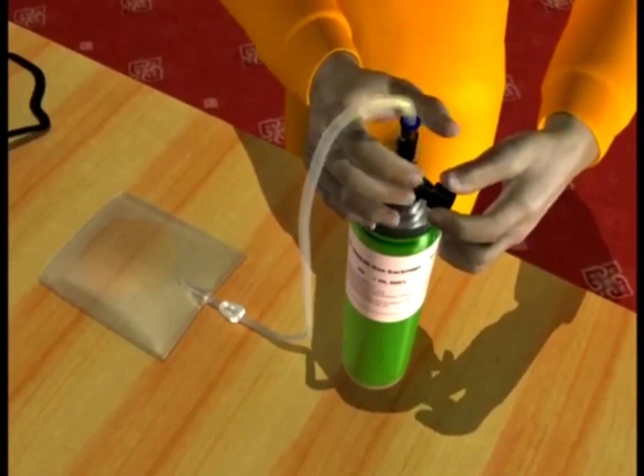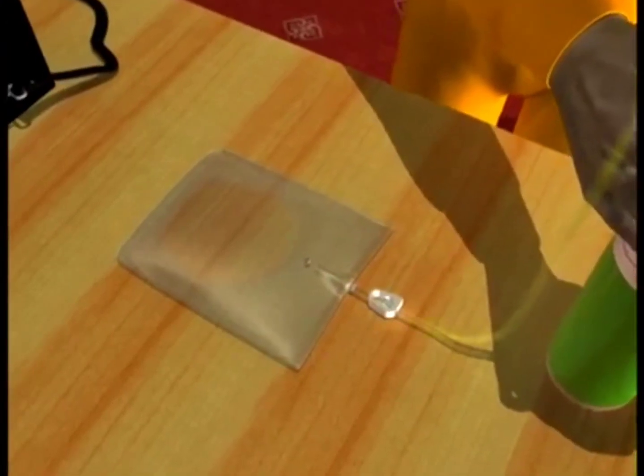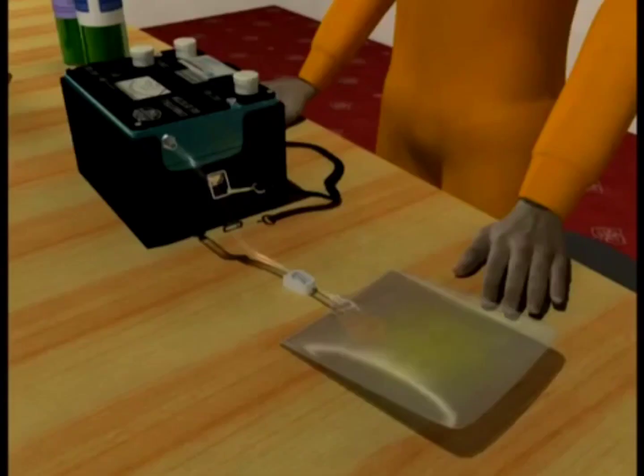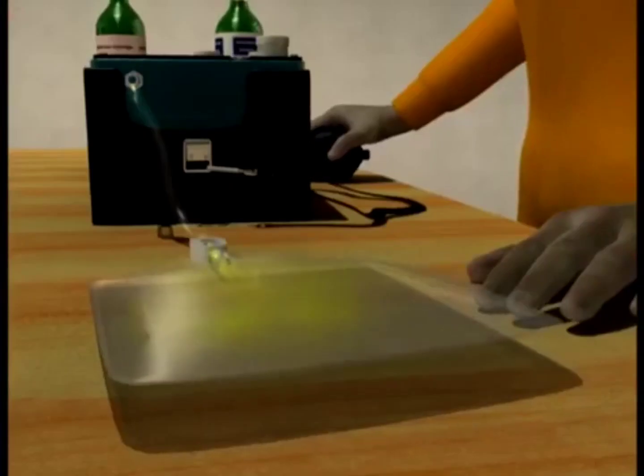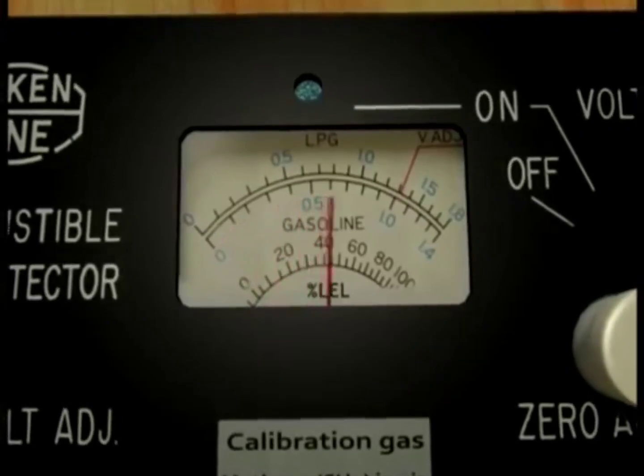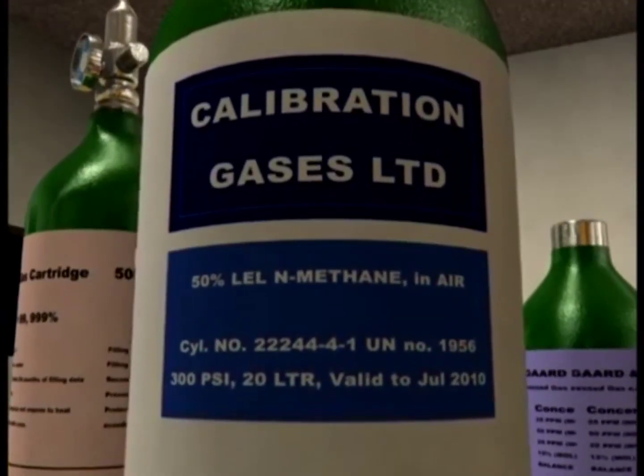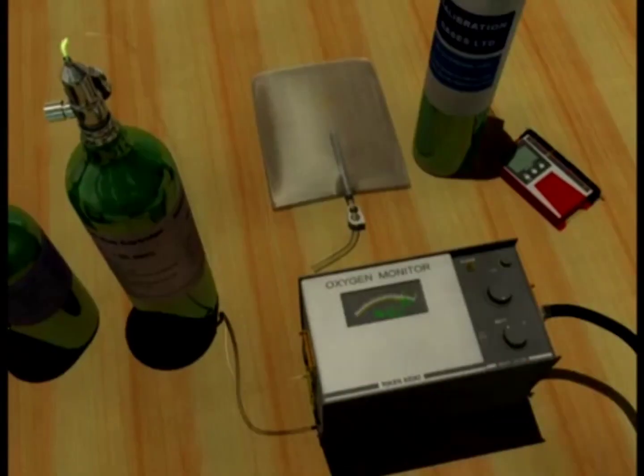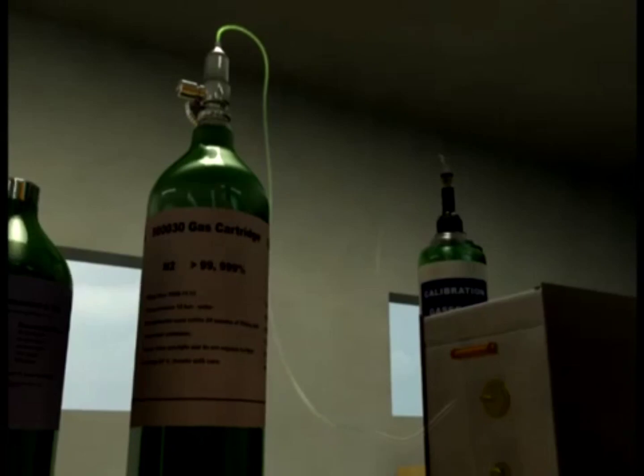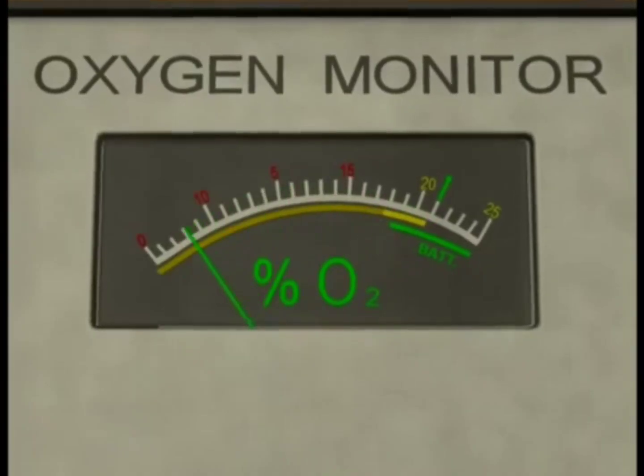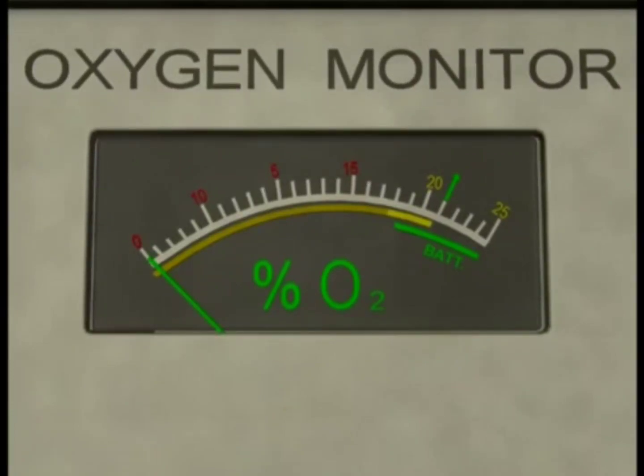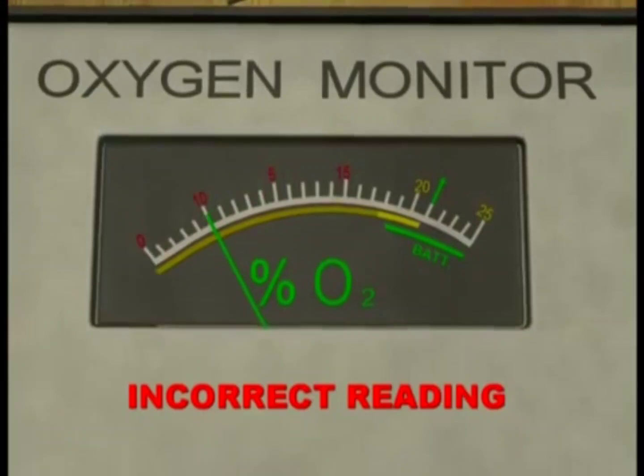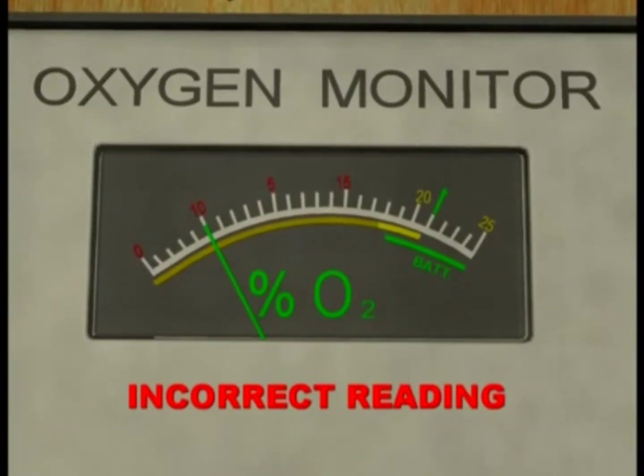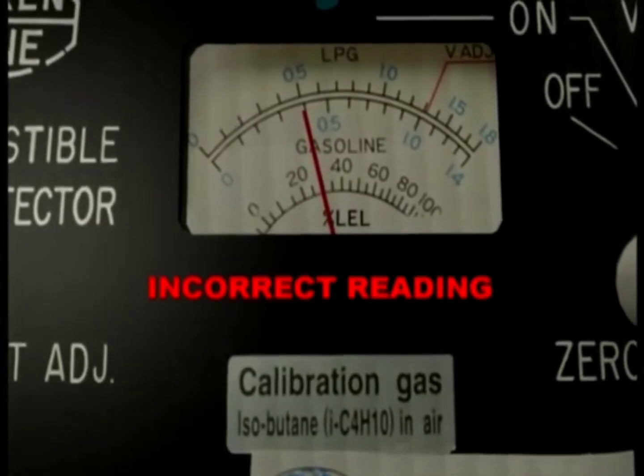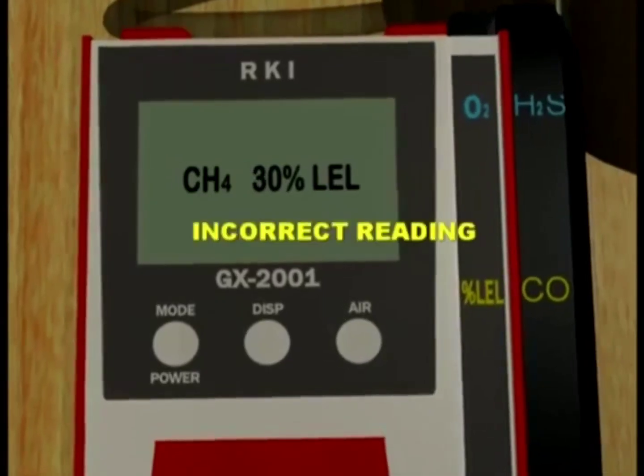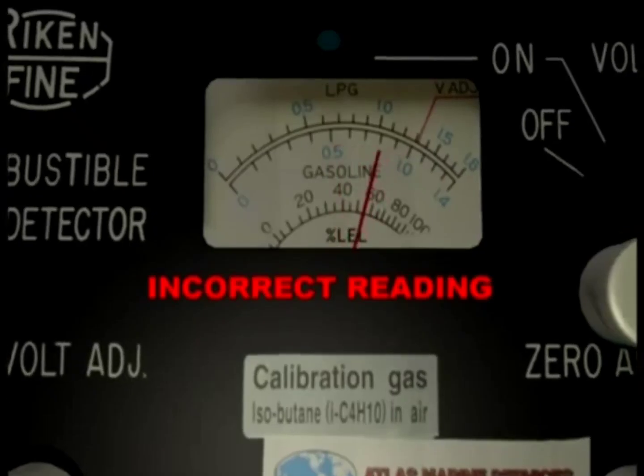The gas may be transferred from the bottle to a collapsible plastic bag designed for the calibration purpose. This bag is then attached to the meter at the inlet for calibrating. The reading of the meter can then be compared with the calibration values as marked on the span gas bottle. An oxygen meter, when calibrated using 99.99% nitrogen, would give a reading of 0% on the scale. A different reading would indicate a faulty meter requiring attendance. Similarly, if any of the meter reading during calibration is different from that marked on the span gas bottle, it would indicate a defect needing attention.